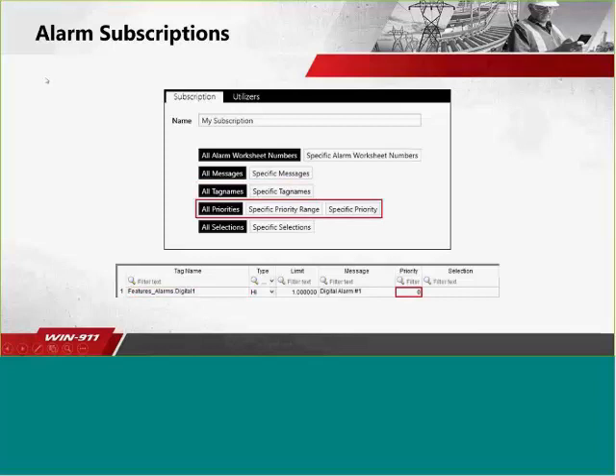We can also do priority. So in Web Studio, let's say 0 is your high priority. I only care about high priority alarms. So I create a subscription that says, give me all the alarms that are priority 0. Then if an alarm occurs at that priority, it comes into WIN911. Maybe this subscription, you set it to a call-out list that notifies people immediately. And you have another subscription that brings in lower priority alarms and sends to a call-out list that has a built-in delay of maybe 10 or 15 minutes to give the alarm some time to normalize before actually calling anyone.